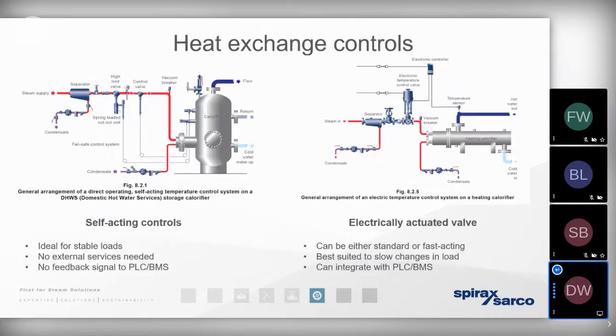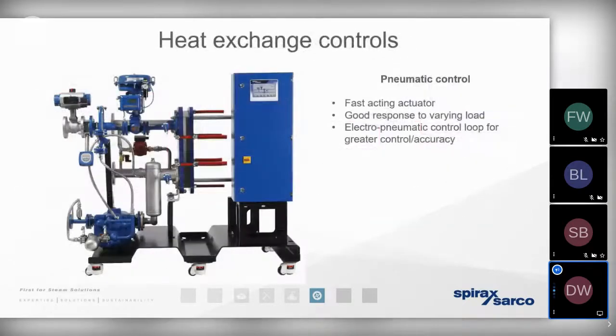But if we want to generate sources of hot water from steam instantaneously and on demand, then it's highly likely that we are going to need to increase the sophistication of the controls and move from a self-acting to a control valve that's going to have the P plus I or even the P plus I plus D control philosophy. So we can now bring all of those benefits together onto a fully packaged heat exchange solution to ensure that we get a very accurate and responsive control.